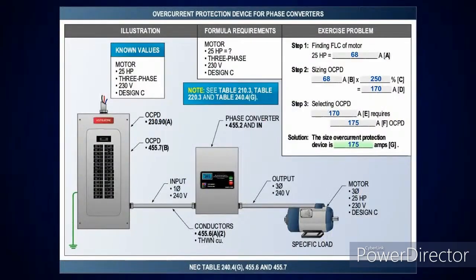So, where we left off last week on the homework was dealing with the phase converter. I said you need to go over and look at 455.7b when you have a fixed load like this. But in that text, it's going to refer you to 455.6a2. When you pick that up on your fixed loads, when you're dealing with that conductor, you're going to take it at 250%. And I said the rule of thumb is this: when you're sizing the overcurrent protection device, any percentage at 125% or less, you go up to the next standard size. Any percentage above that, you drop down to the next standard size.